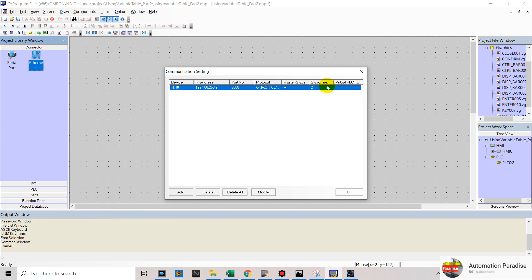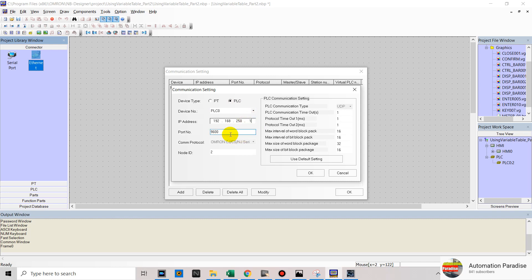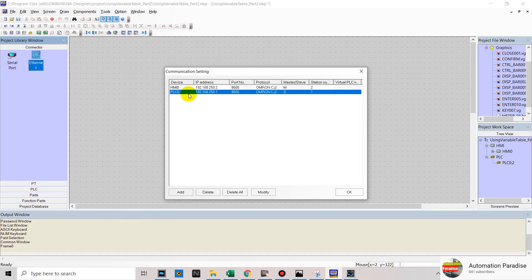Now we will add our PLC communication setting. In device type, select PLC. Then in IP address, we will change to 1. Then in port number, we will use the default 9600. Then in node ID, we will change to 1. And click OK. Now we have already added our PLC0 communication setting.